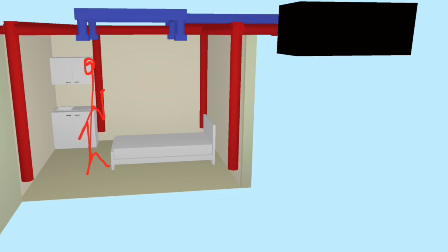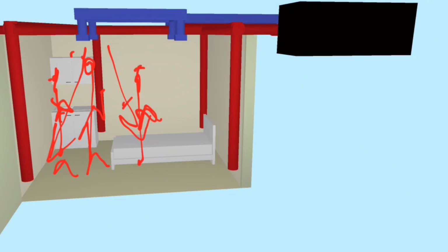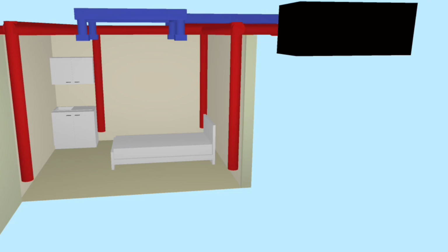But that again means that only the people who stay right close to him might be infected, and actually the fact that all the air goes down still reduces the possibility of them getting infected. So that's how, just by modifying, adding a little, instead of one big outlet, you add more smaller ones, and the same thing you do with inlets, and you drop them down. This simple modification will cost you probably just a few bucks, and would actually change things dramatically.